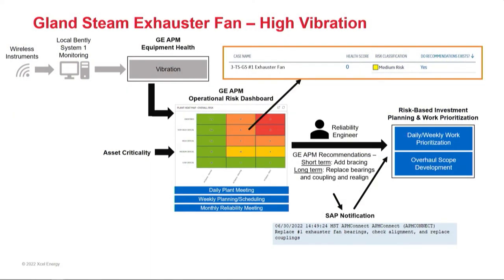Another example: our gland steam exhaust fan and motor on one of our units. We added wireless instrumentation to the fan and motor assembly. That data went into our local System 1 server, we connected it to Pi and brought it into APM, set limits around it, and the vibration was excessive. Combined with criticality, it populated as a medium risk on the dashboard. The engineer worked with our vibration SME to diagnose it further, added stiffening to the structure to reduce vibration levels, and created a recommendation for long-term risk mitigation — replacing bearings, replacing the coupling, and realigning the fan and motor. That created an SAP notification and is now being worked through our normal overhaul planning and work management process.